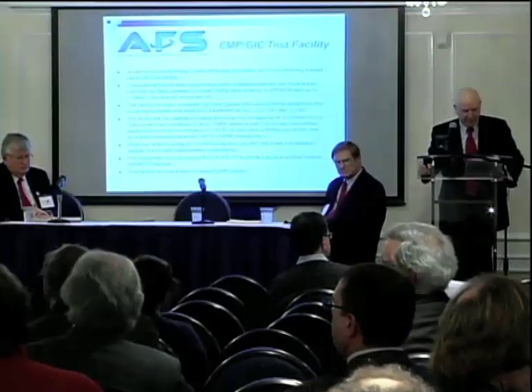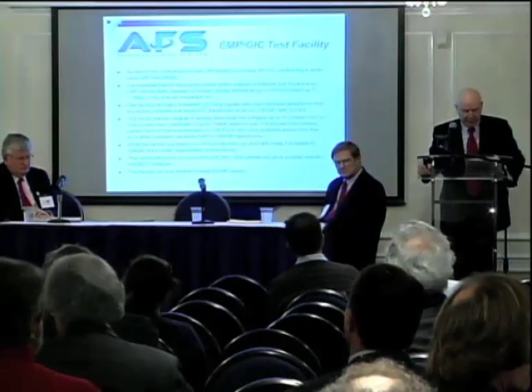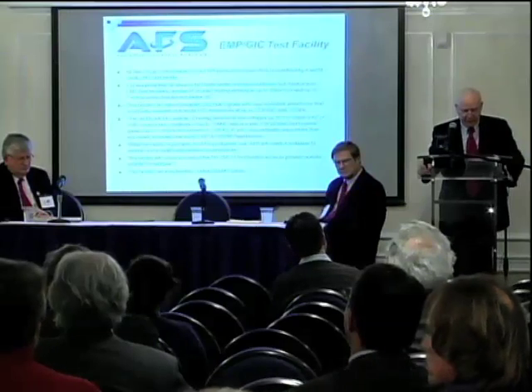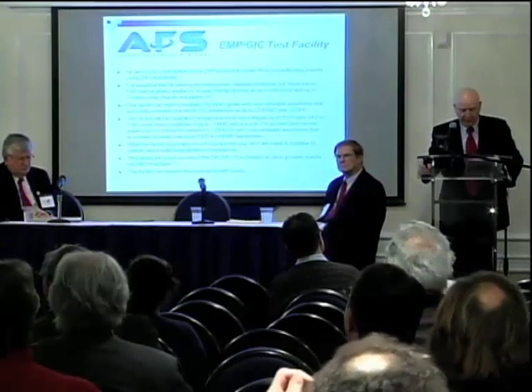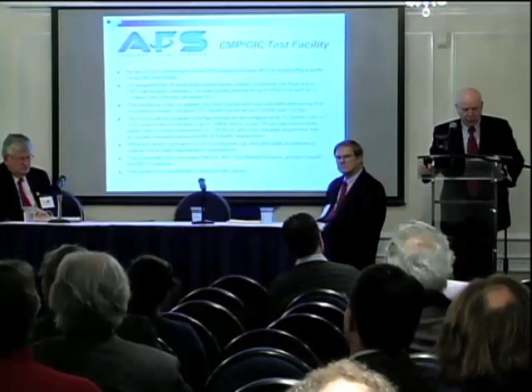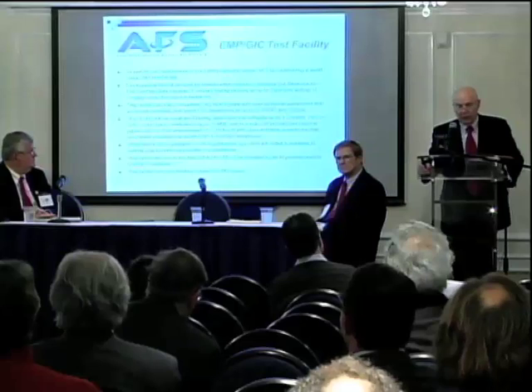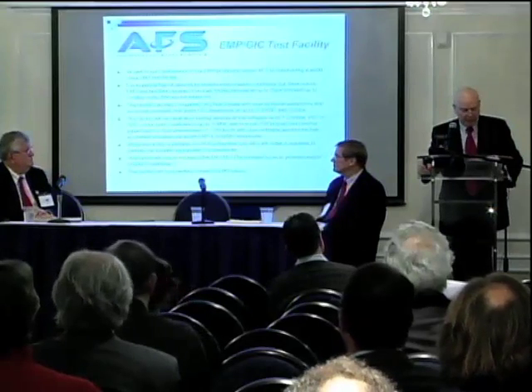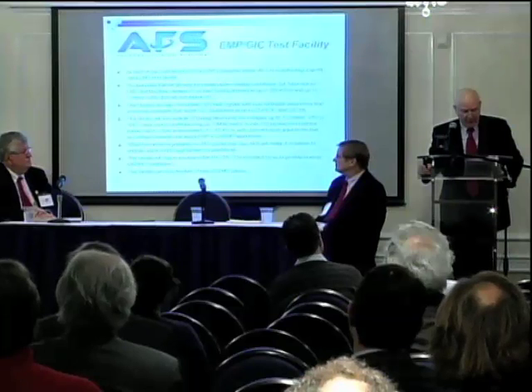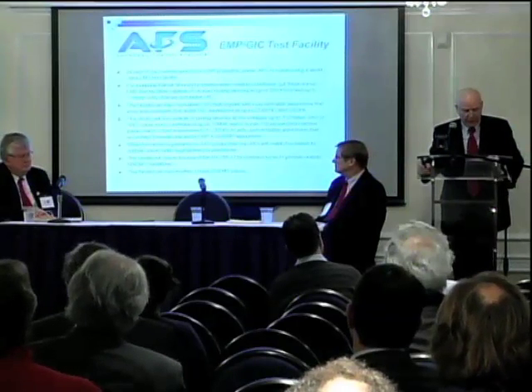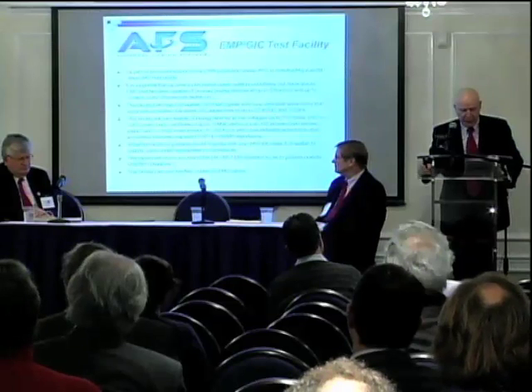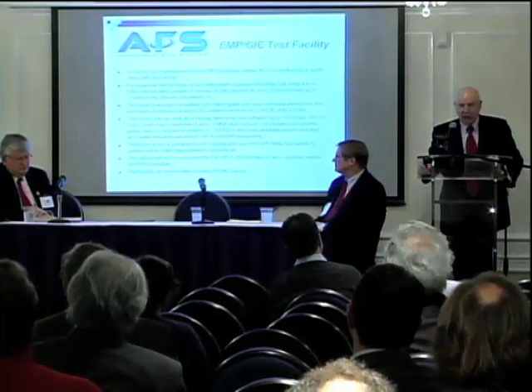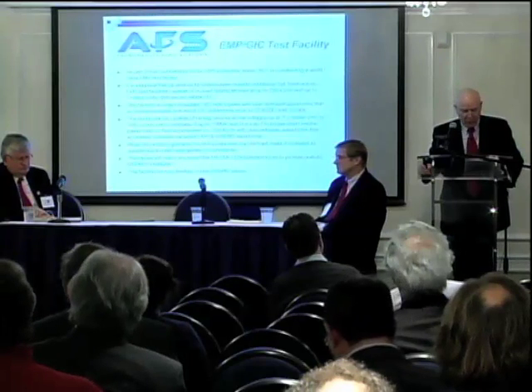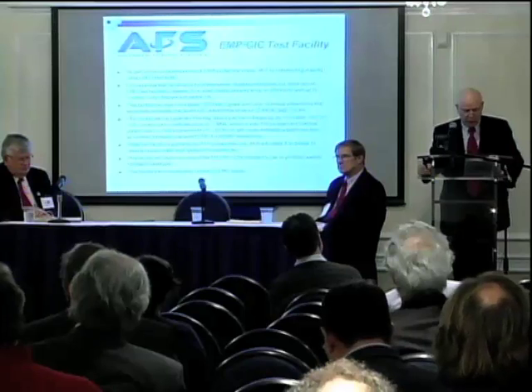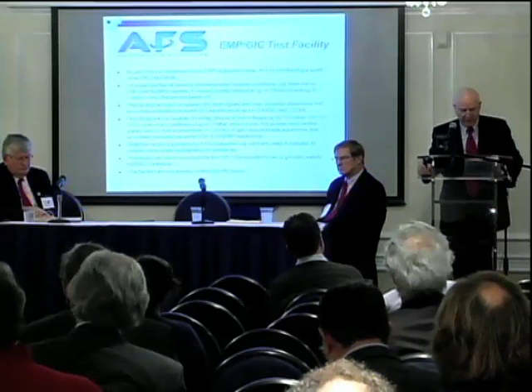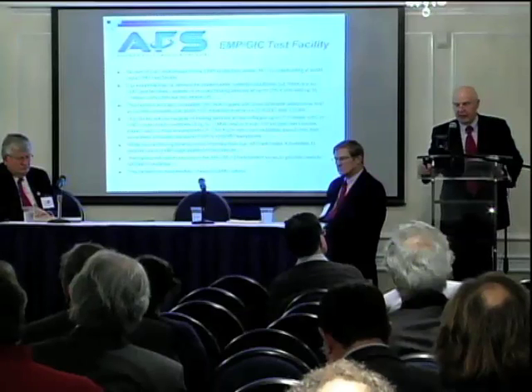EMP test facilities for on-load testing of devices at up to 250 kV per meter and up to 1 million volts are what we're doing, and we're not aware of anything else where that type of test is available. This facility can inject simulated GIC fault signals with a user-definable waveform that accurately simulates real-world GIC waveforms up to 25 kV DC and 100 kA.